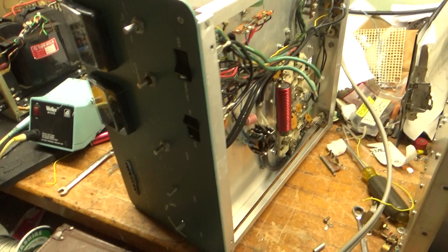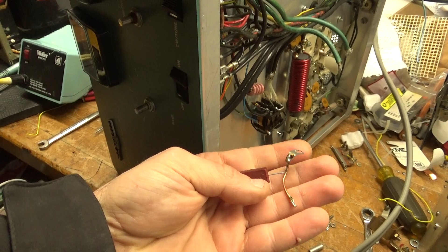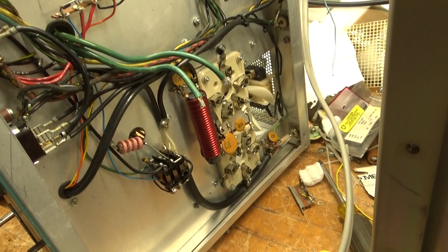So I'm going to talk about this one first. Filament transformer's no good, sourced another one. Grids were not grounded properly, had a single wire for one grid connection to ground. Took that out, grounded them properly with copper strap. Needs new circuit breakers, one was open.